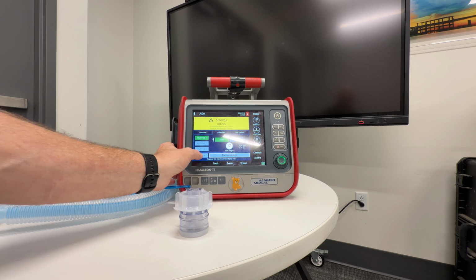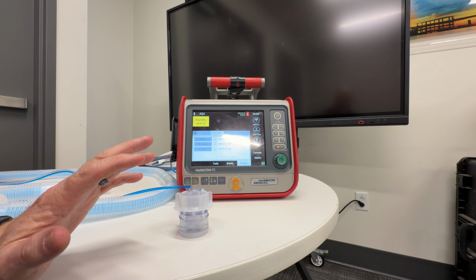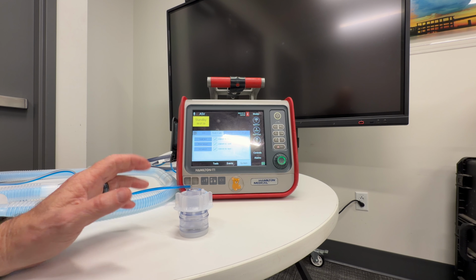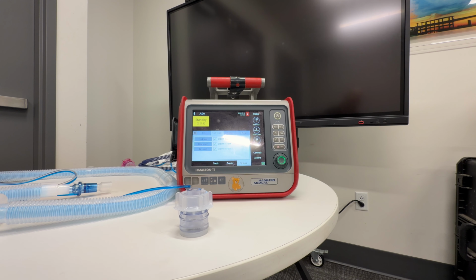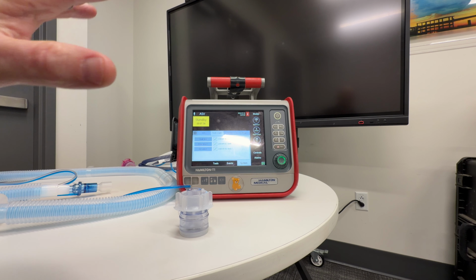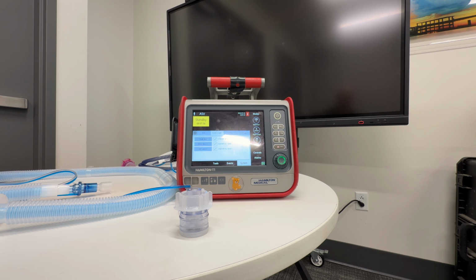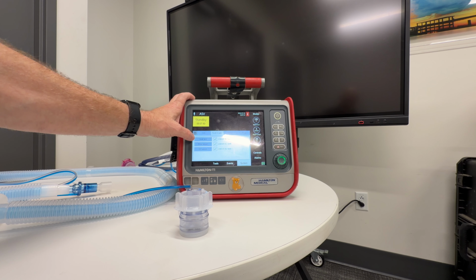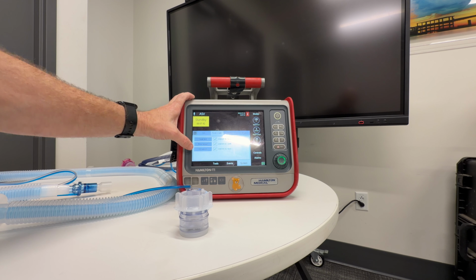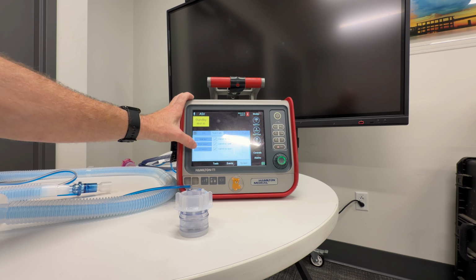Now, the ventilator that we normally use has a different user interface. This is a spare, but it's all I've got right now to do it. But it's pretty similar. You just go to adult and you go to pre-op check. You're going to see 3 different checks that we're going to do here. We've got a leak test, a flow sensor, and an O2 sensor. The most important one right now that I want you to really focus on and learn how to use is the flow sensor.